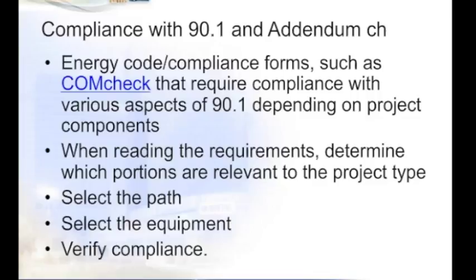Thanks, Jason. One of the first things you need to do using Addendum CH is to obviously read it. Path A or B, which we'll talk about here in a little bit, is one of the first things you need to do, because the numbers for full load and part load values are obviously different. You need to select what type of equipment, whether it's water-cooled, air-cooled, or positive displacement, or a variety of different types of equipment. Each one will have different requirements based on the tonnage. And after that's done, verifying compliance with the addendum and 90.1 is obviously important from a consulting engineer standpoint.